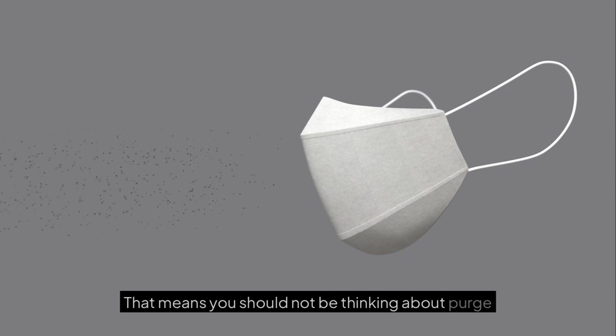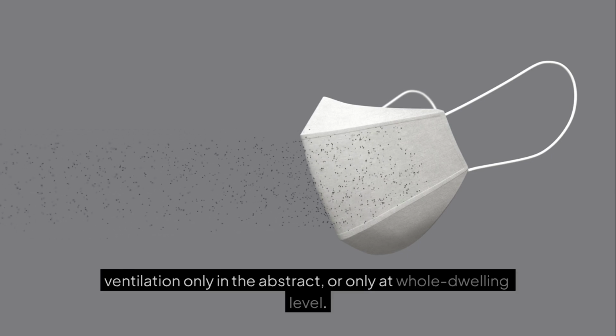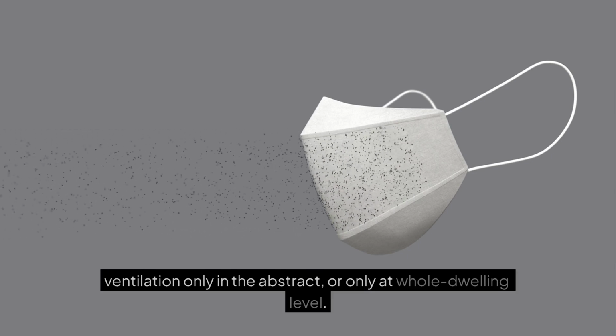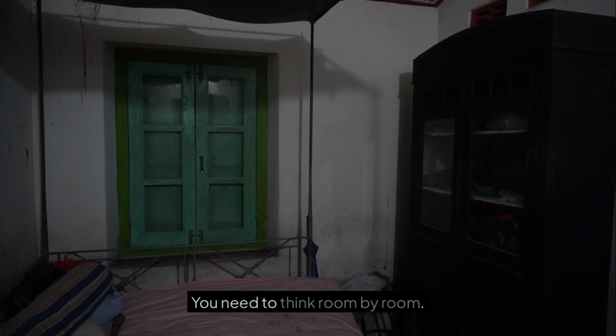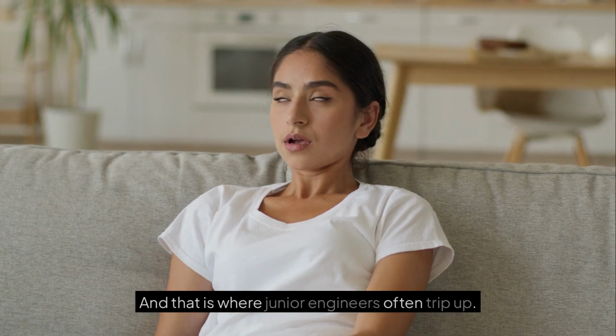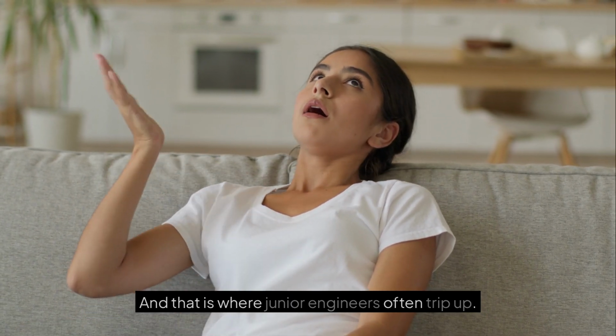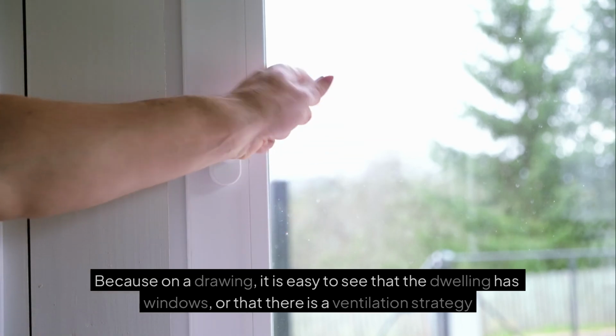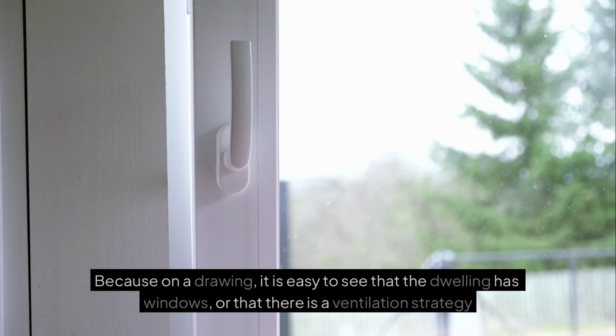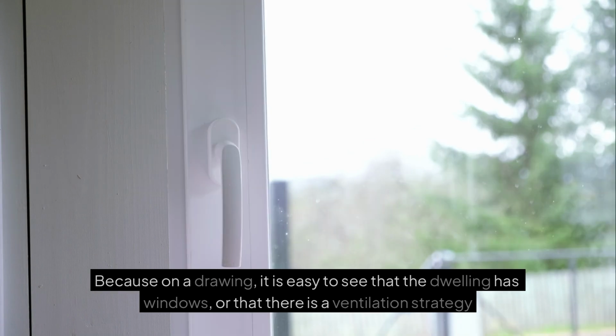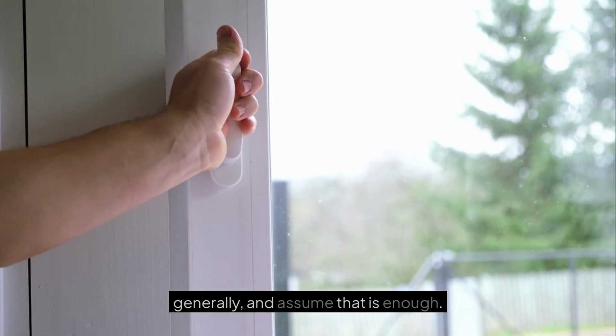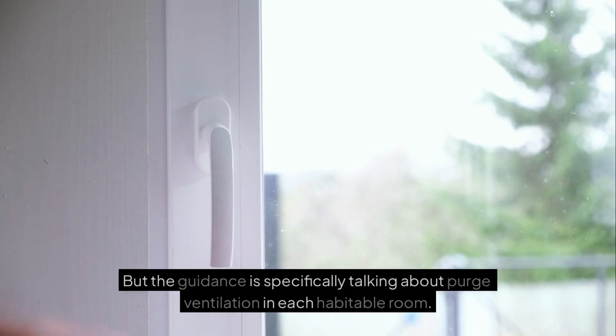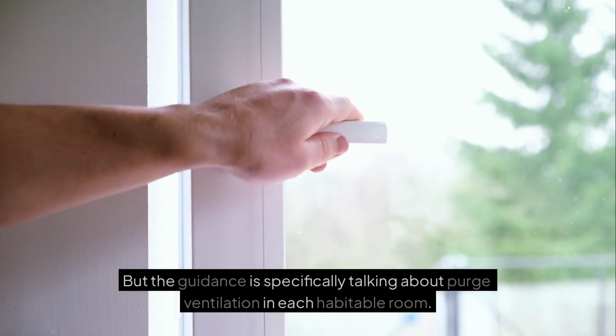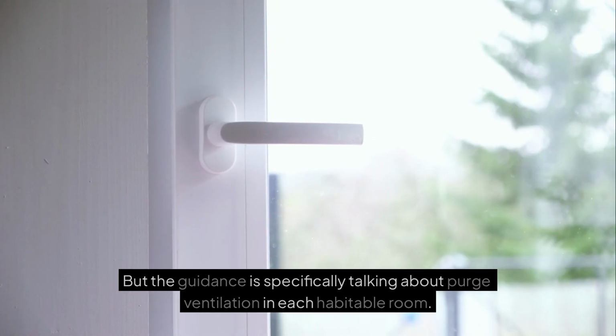That means you should not be thinking about purge ventilation only in the abstract, or only at whole dwelling level. You need to think room by room. And that is where junior engineers often trip up. Because on a drawing, it is easy to see that the dwelling has windows, or that there is a ventilation strategy generally, and assume that is enough. But the guidance is specifically talking about purge ventilation in each habitable room.